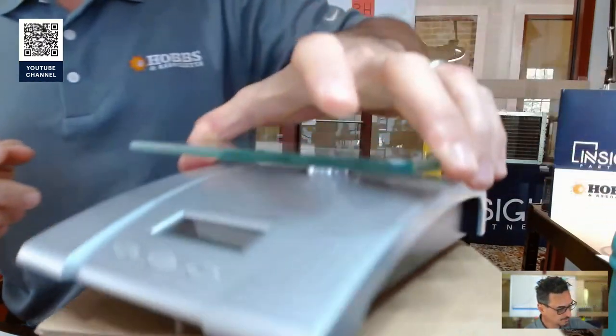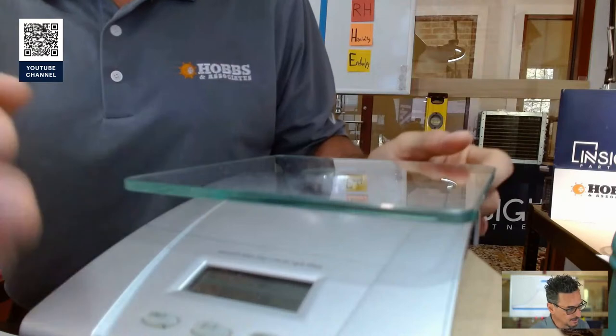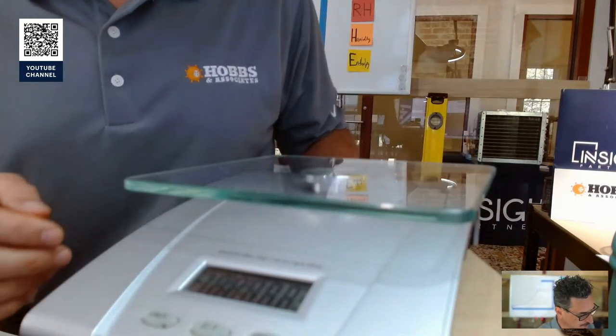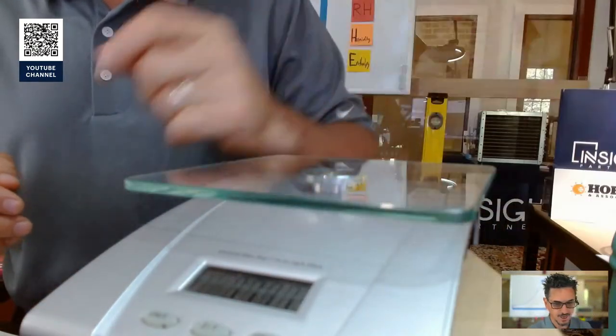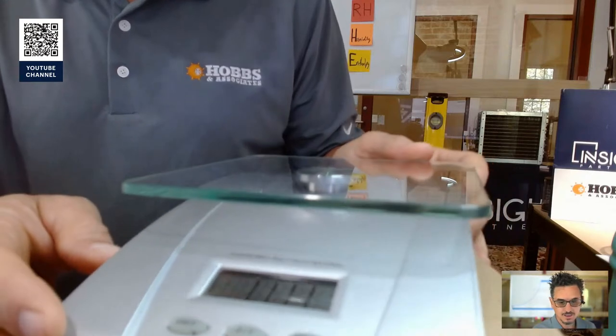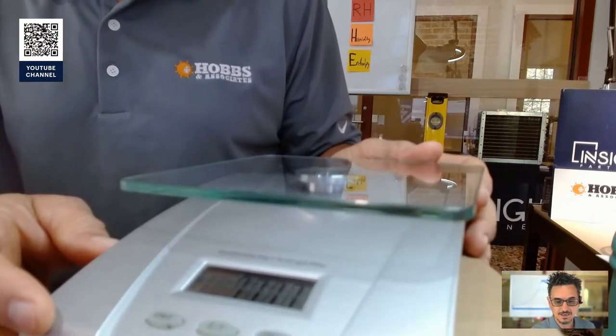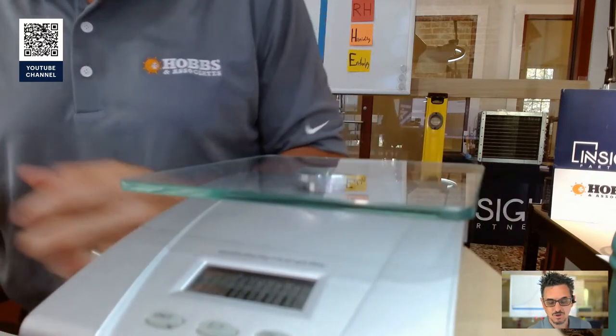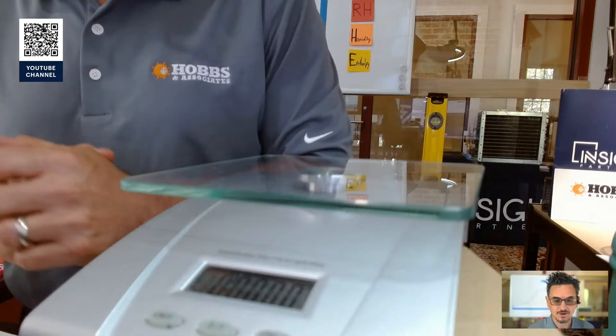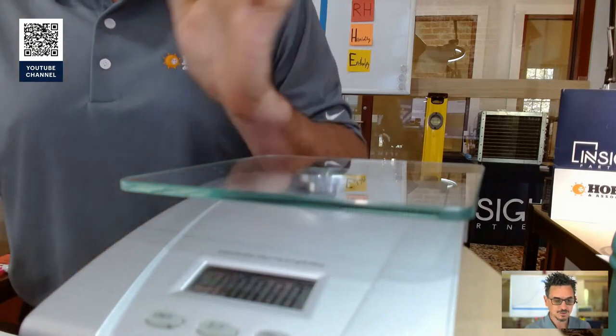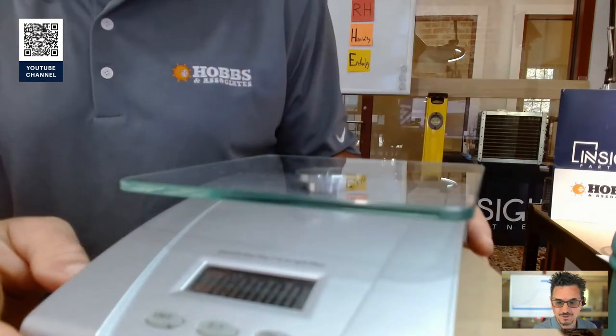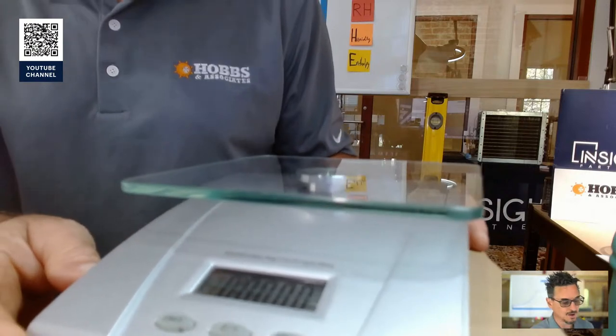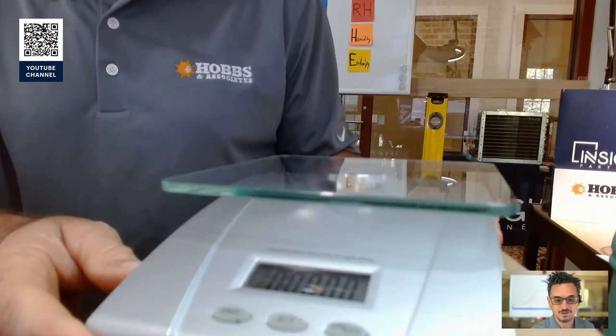So, relative humidity. Now, often confused with humidity. This is a big deal, to understand the difference between relative humidity and humidity. The humidity in the air is the actual amount of moisture in the air. It is not contingent on the temperature of the air. It doesn't care what the temperature is. It's the physical amount of moisture in the air at a given state.